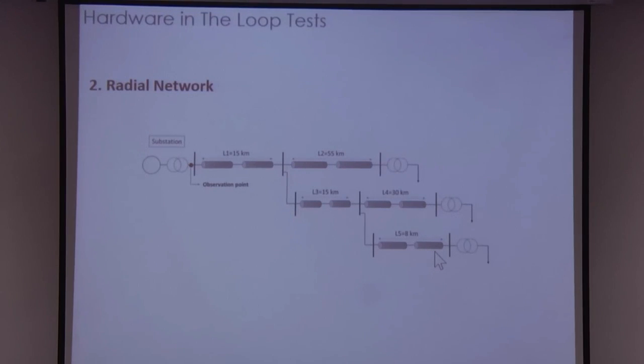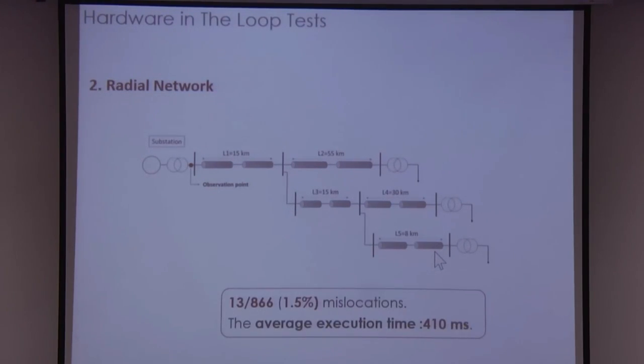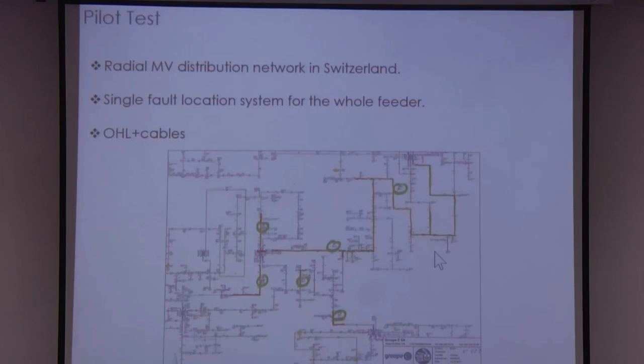For the three-phase radial network, we did the same hardware-in-the-loop test with more tests, 866 fault cases. Only 13 times the system failed with some error. And at the end, we took our prototype and installed it in a live power network, a medium voltage distribution network in Europe, in Switzerland. This is the single line diagram. This was the substation where we installed the system, and this was the feeder we did the test on.